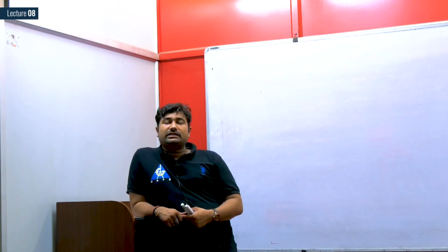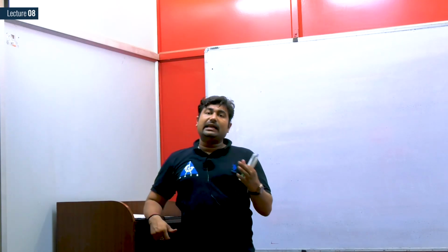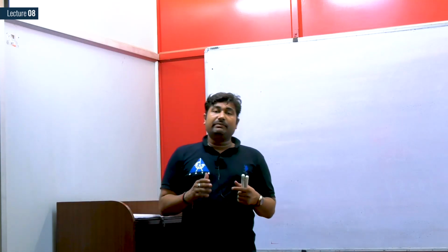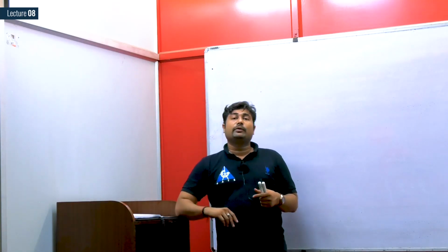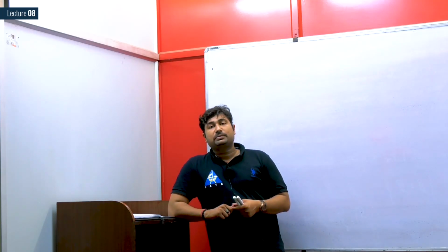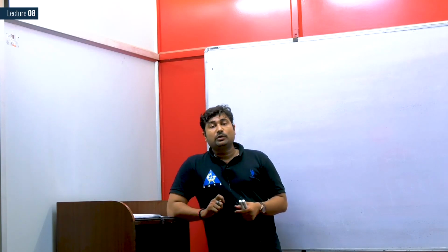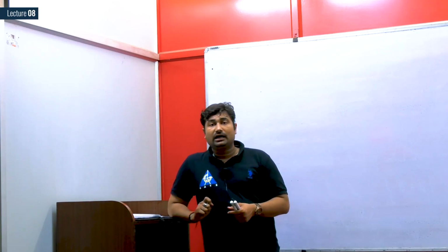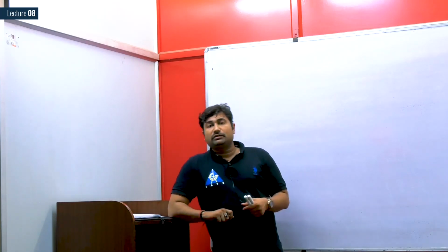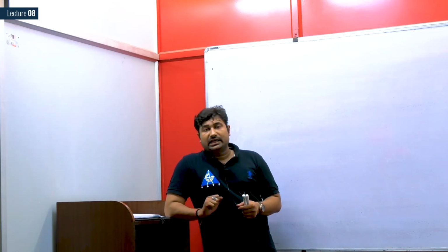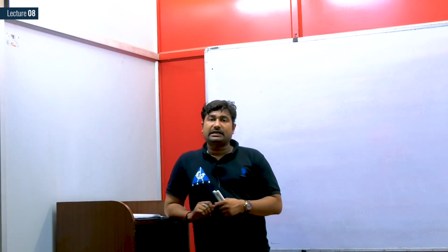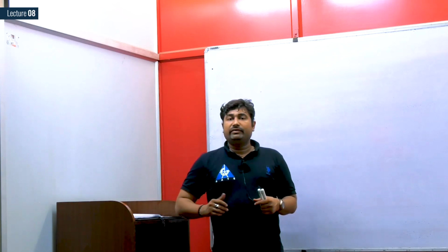While eddy current loss can be reduced by thin lamination, usually 0.35 mm thick, with varnish insulation on both sides. And eddy current loss is also reduced by adding silicon, but not more than 4% of the entire core volume, otherwise the material will become brittle. Okay.